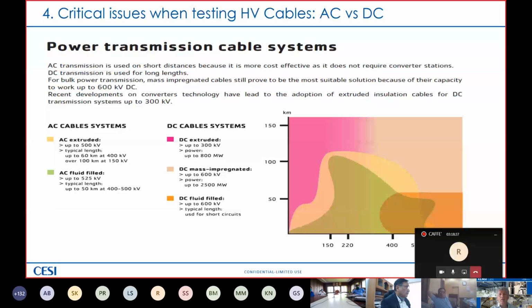The DC cable connection is a must compared to AC because of the compensation you need. So this compensation can be comparable to the increased cost of the converter and the complexity of the interconnection. So nowadays, for interconnections longer than 150 kilometers for sure, both land or submarine cable, the preferred solution is a DC cable interconnection.